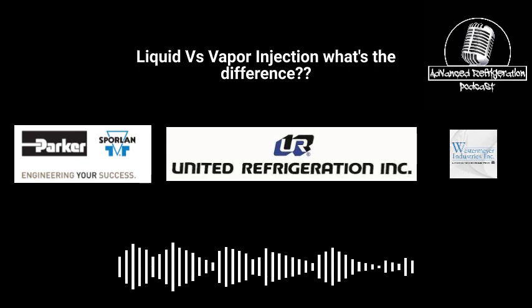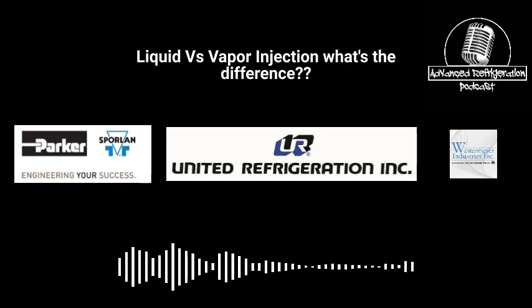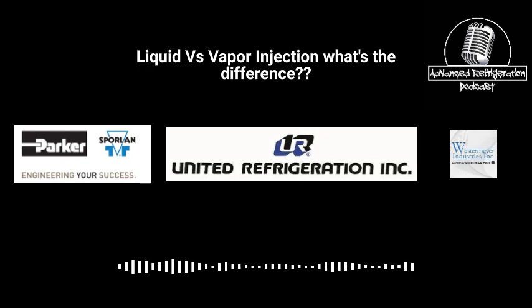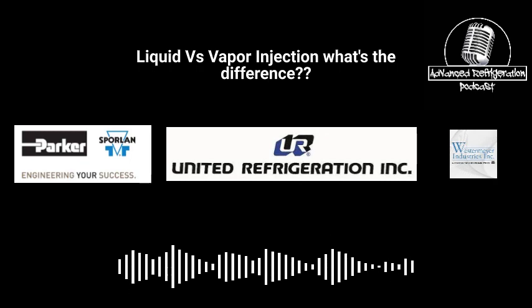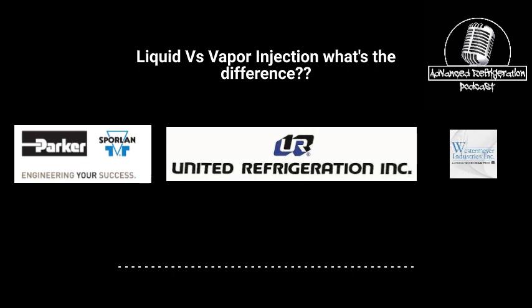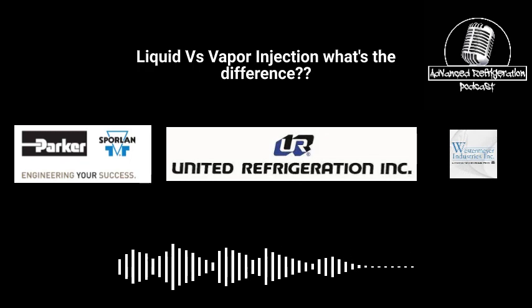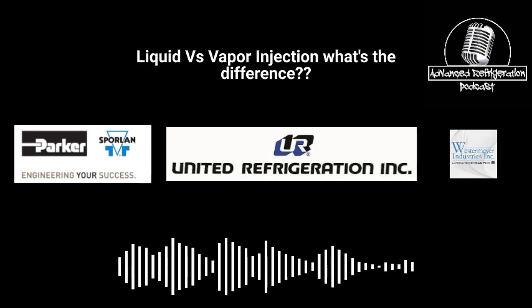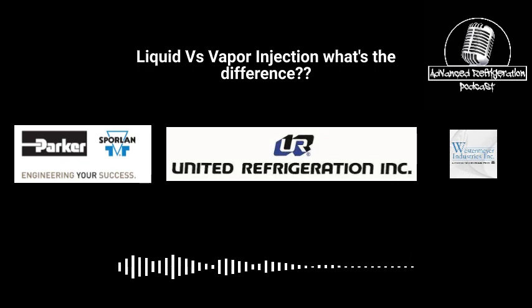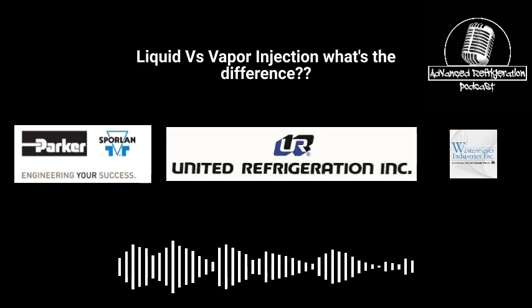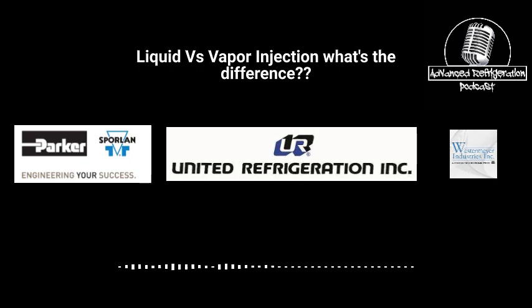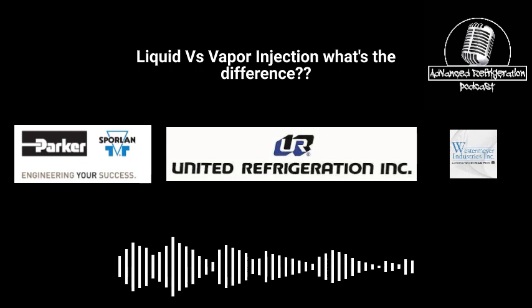We also have vapor injection. Typically, we see these on subcooled circuits, subcooled racks. The suction that comes off of the EPR, that's holding that evaporator pressure regulator for that braze plate heat exchanger, the outlet of that, the suction is typically going to the vapor injection port. Typically, you'll see the temperature of that be X amount of degrees above the saturated that's supposed to be running. So if we're trying to maintain a 50-degree subcooler temperature, typically we have to maintain 40 degrees to maintain that 50, which means if you set that for 10 degrees of superheat, you should basically get 50 degrees entering that compressor.